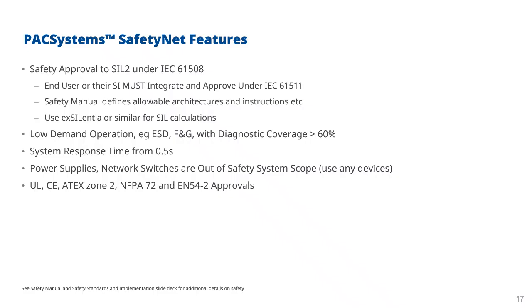And when we talk about system response times, we can get a response time down to about half a second, possibly a bit faster. But a thing about these safety systems is they aren't designed to operate very quickly. If you're talking about machine safety, you might want operation down to 10, 15, 20 milliseconds to stop the operator from being harmed.